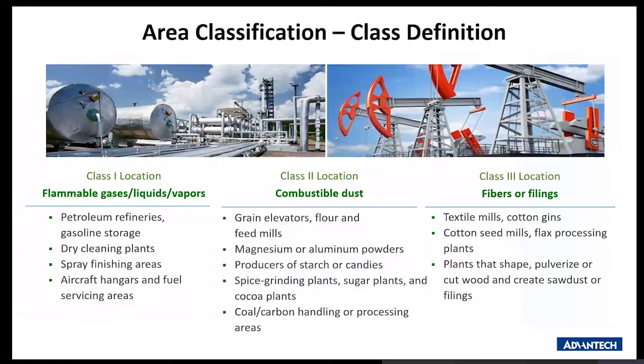On the general scale, looking at the area of classification for C1D2: Class 1 locations are classified as flammable gas, liquids, and vapors associated with petroleum, dry cleaning plants, and spray finish areas. Class 2 locations consist of combustible dust, and Class 3 locations consist of fibers and filings.